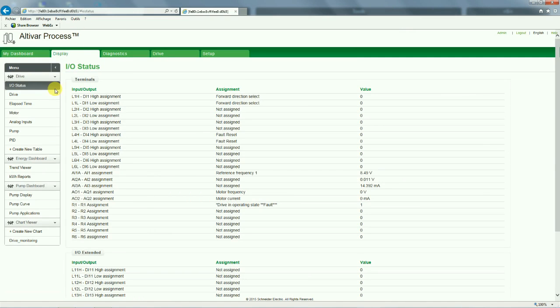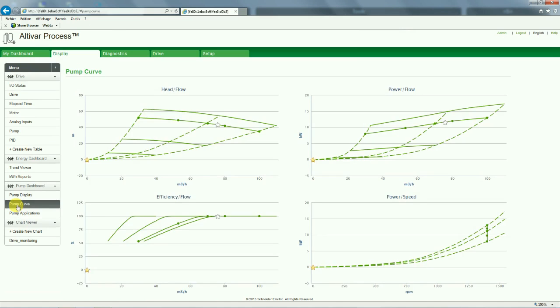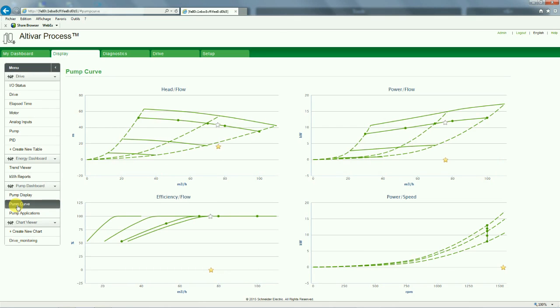When you go back to the display tab in the pump curve, it's updated according to the inserted points. By giving a run order to the pump, we can observe that the working point in yellow star moves in direction of the best efficiency point in white star.